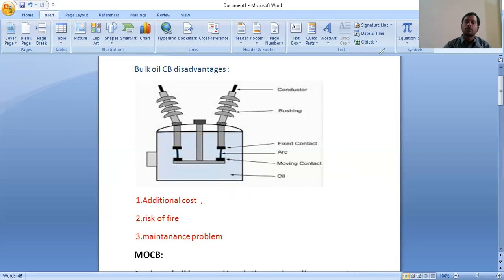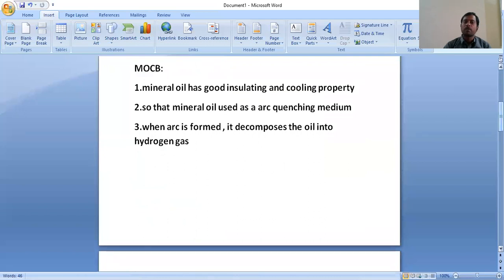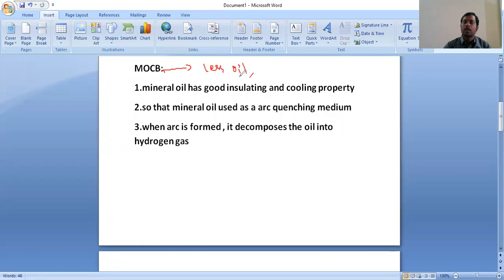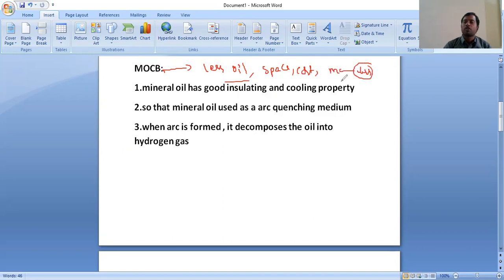To overcome the above problems, we should use a minimum oil circuit breaker. The minimum oil circuit breaker has less oil compared to the bulk oil circuit breaker. Due to having less oil, space requirement is less, cost is less, maintenance is less, and operation is also very fast. The mineral oil used is having good insulating properties and cooling properties.